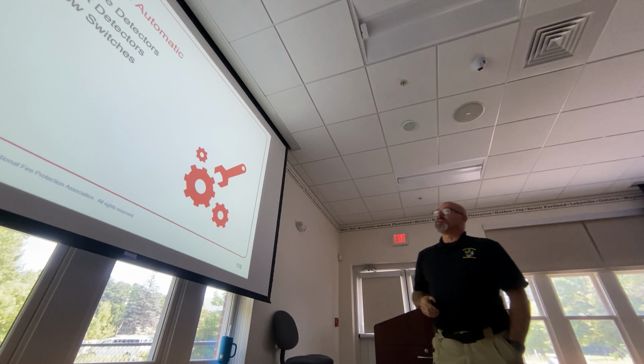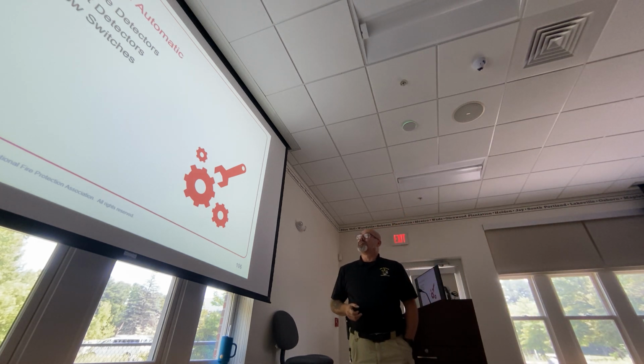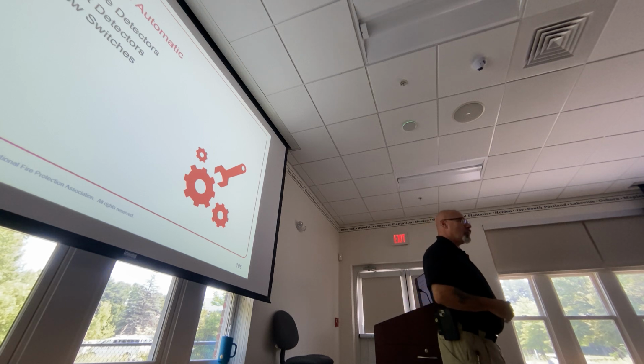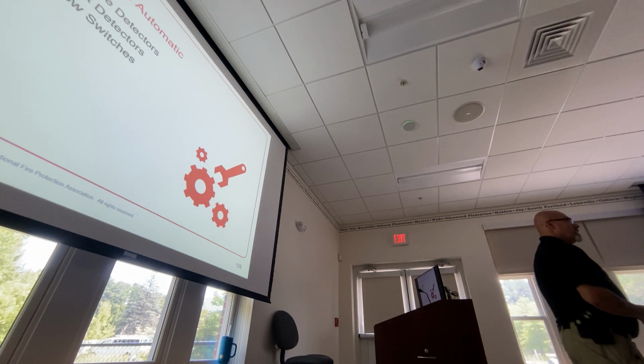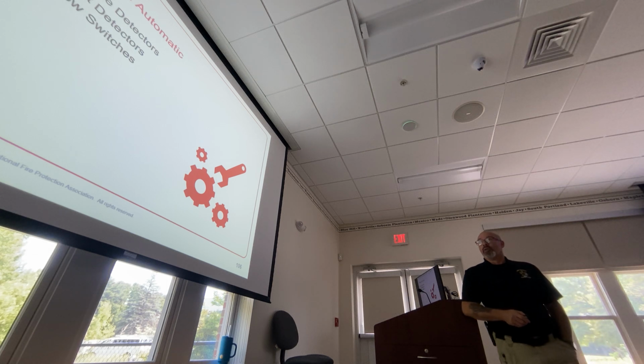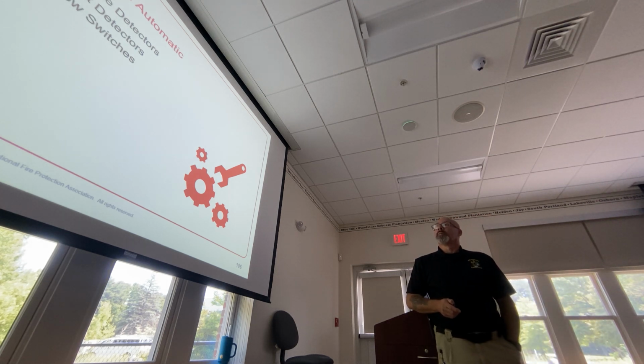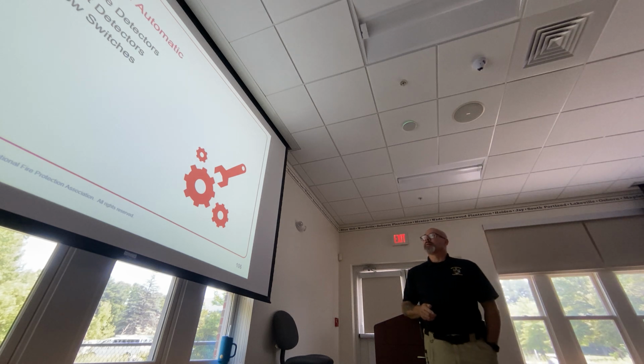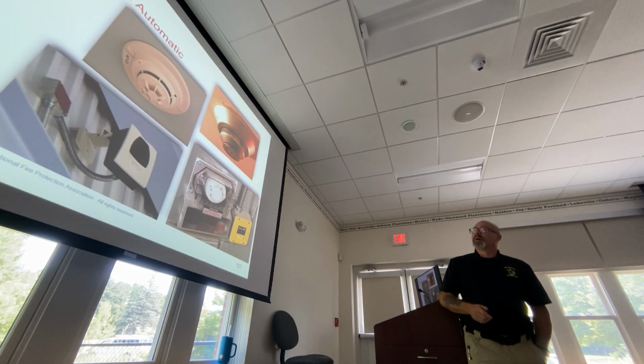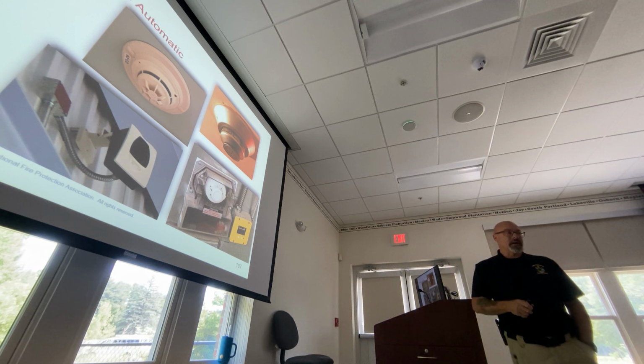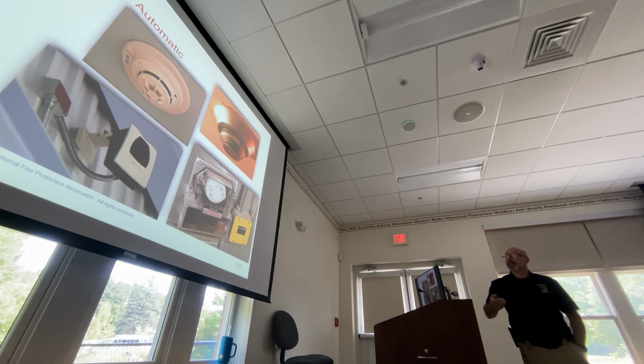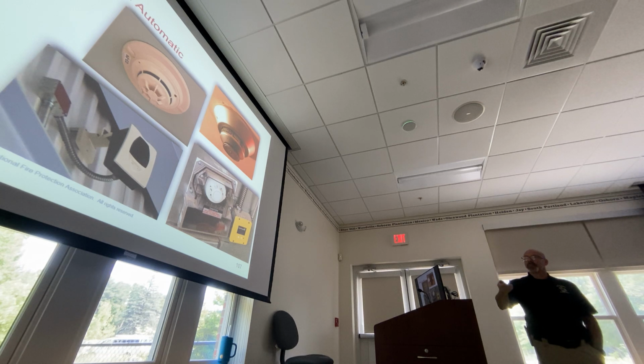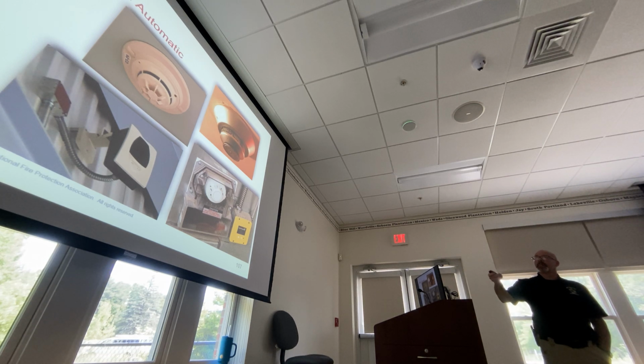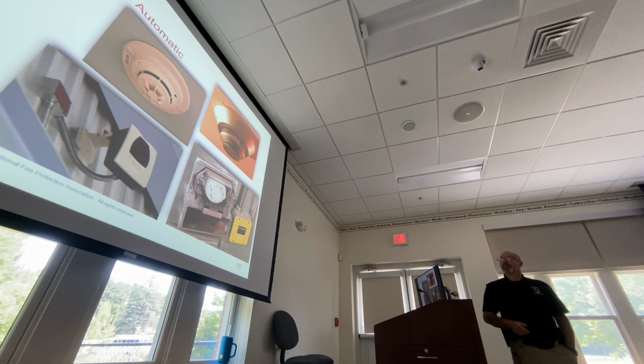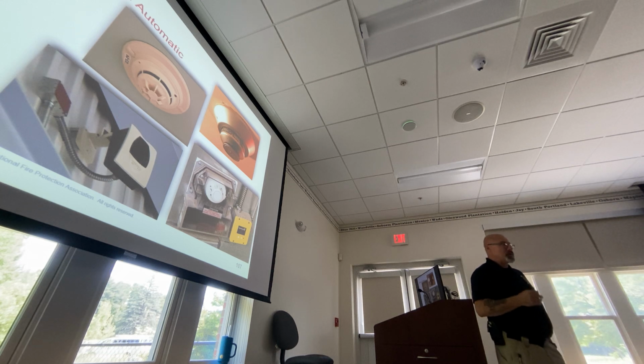So for automatic initiation, smoke detectors are considered automatic, and so are heat detectors, otherwise known as rate of rise detectors. Water flow switches are automatic. Here we have some examples of automatic detectors. This is an automatic detector. What is this? It looks a little funky. That is a rate of rise, meaning a temperature.